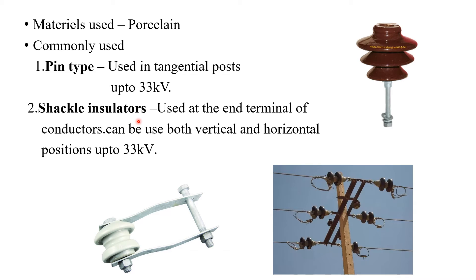Now let us discuss the major types of insulators used for overhead transmission systems. The first type is pin type insulators. They are mainly used up to a voltage range of 33 kilovolts and used in tangential posts. The next important type is shackle insulators. Shackle insulators are mainly used at the end terminals of the conductors and can be used for both vertical and horizontal positions, whereas pin type can be used for tangential position only.